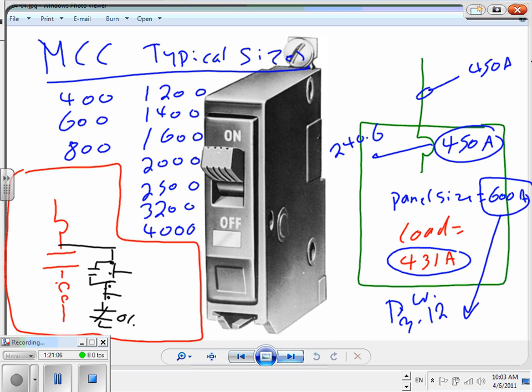So here's what a bucket is. He was talking about buckets yesterday. Here's what a bucket looks like, guys. All this stuff in one bucket. If you open this panel, would you see a contactor in that panel? You see the overcurrent device. Suppose this is a 225 amp. Well, let's make it more realistic. Let's say this one was a 50 amp overcurrent detection device. Here's a NEMA. Remember the NEMA standard, guys: contactor, overload, the control circuit, all in one big bucket.